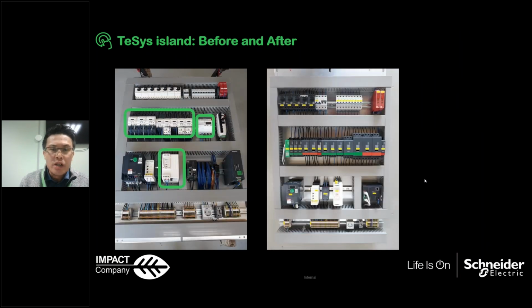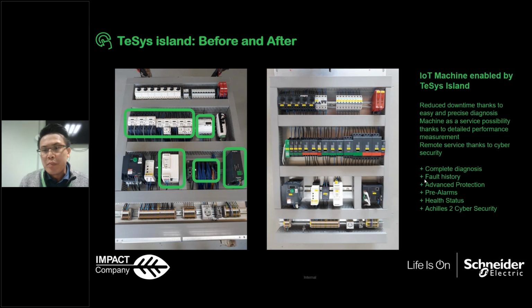So in terms of the physical size inside the panel, you will see before and after. Before, equipped with the TeSys Island, you will see that we need a lot of contactors for the overload protections, a lot of wiring, and then you will have power meters to measure the energy for the panels. But this energy is only for the whole panel. It's not for the individual motors here.